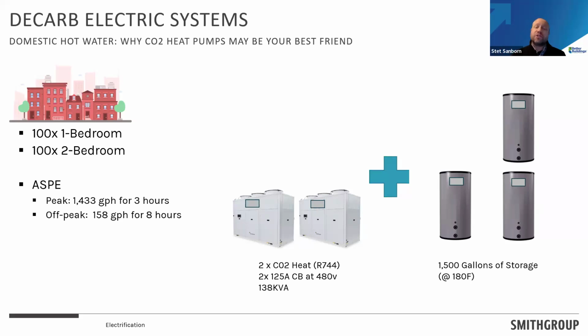This is a great solution for those of you that are space constrained and trying to do a retrofit. But look at the bottom of the slide: instead of 176 kVA, just by changing the type of heat pump, I'm going down to 138 kVA. That's a substantial difference in what the switchgear and ultimately the transformer will see. So if you're electrically constrained on your site, consider multiple heat pump options to see which ones stay under your electrical connected load limit.